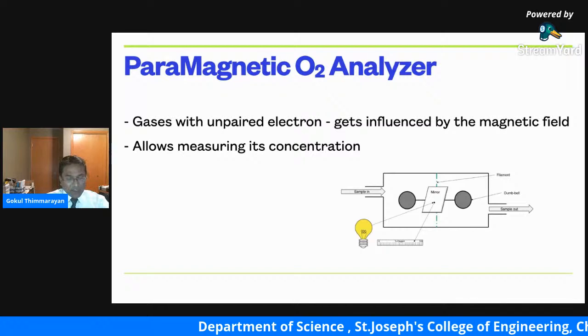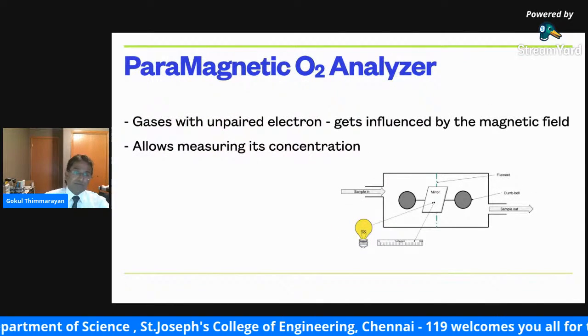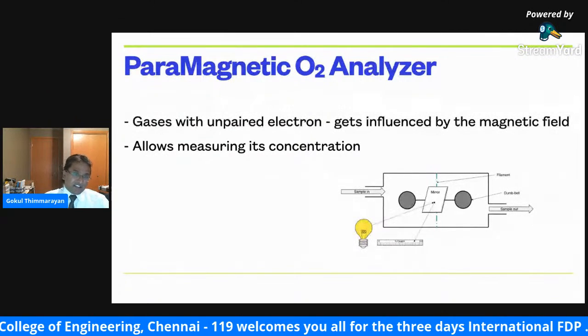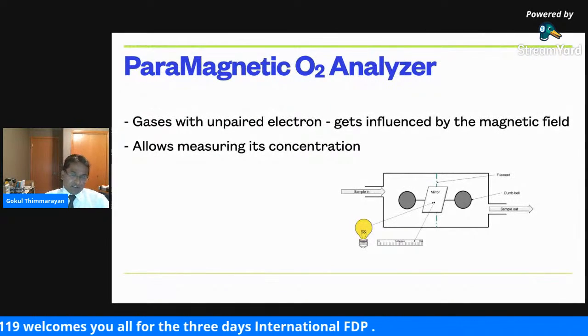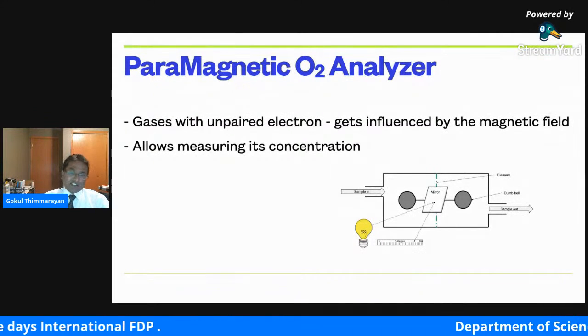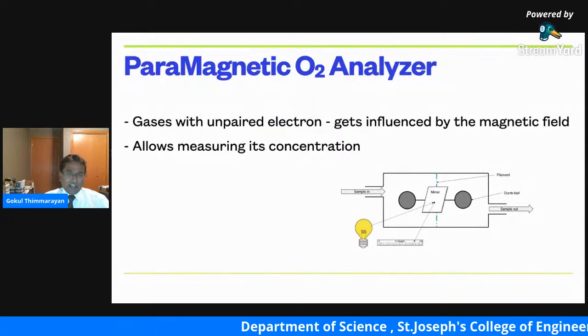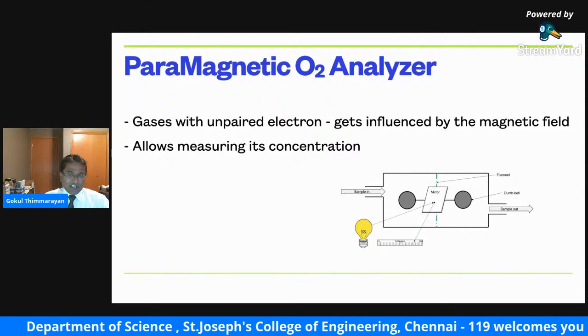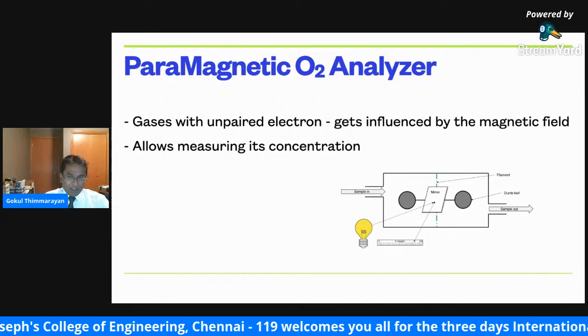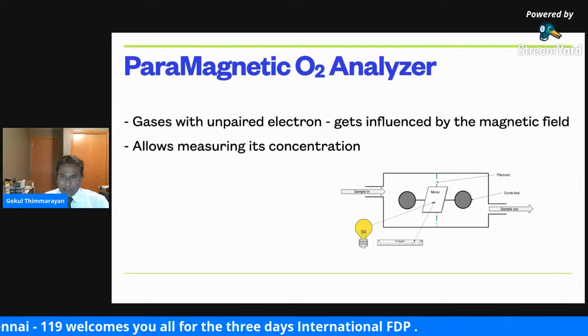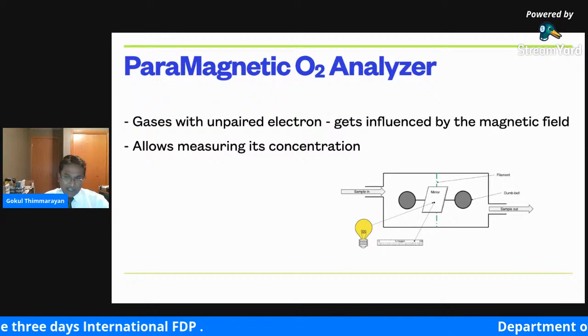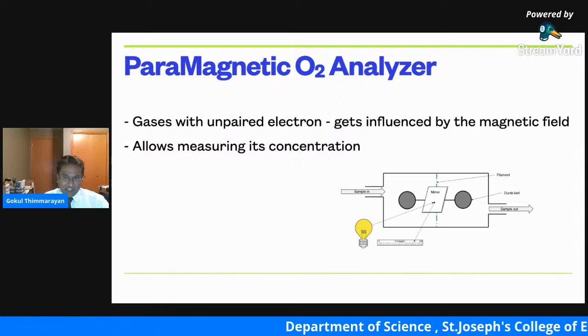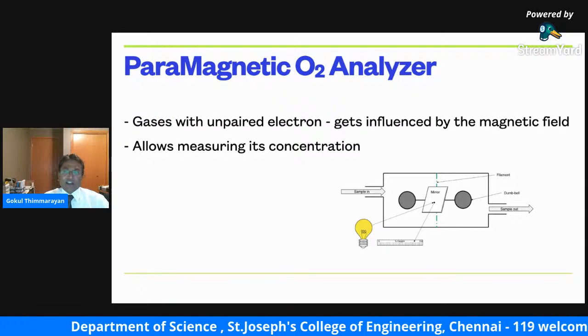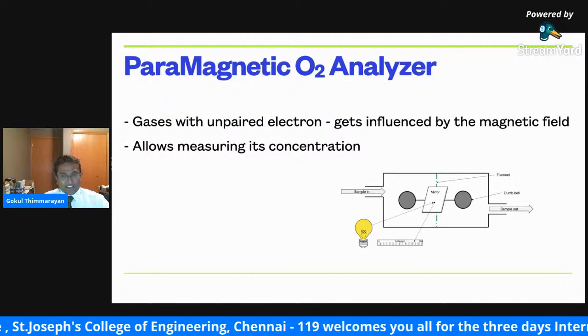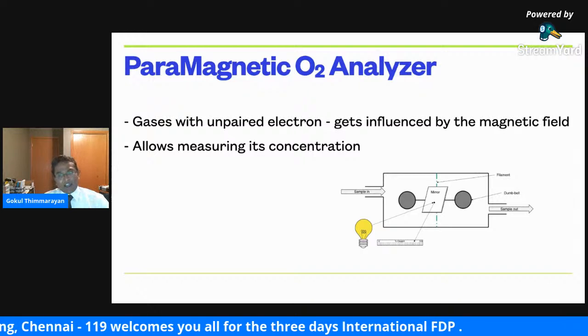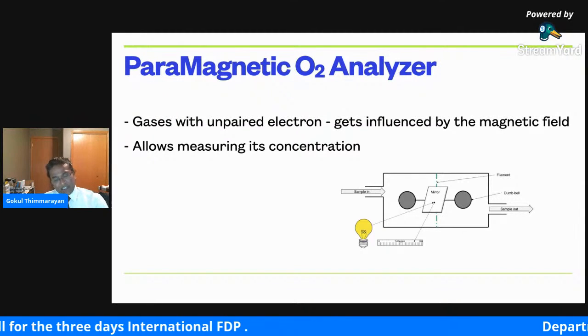That could be done by various methods. Of the various methods, one is the paramagnetic analyzer, where those gas molecules with unpaired electrons get influenced by the magnetic field. So when the sample gas is passed through the apparatus and passes through the magnetic field, it gets attracted towards it and starts spinning the dumbbell, which is this apparatus. Let's not go into discussing the features of the apparatus and how it works. When it passes through the analyzing chamber, it gets influenced by the magnetic field, and it creates a variation in the apparatus from which we could analyze what kind of gas it is and its concentration. Based on the amount of gas in it, it gives us the concentration, and we could also identify which gas molecule is in it.